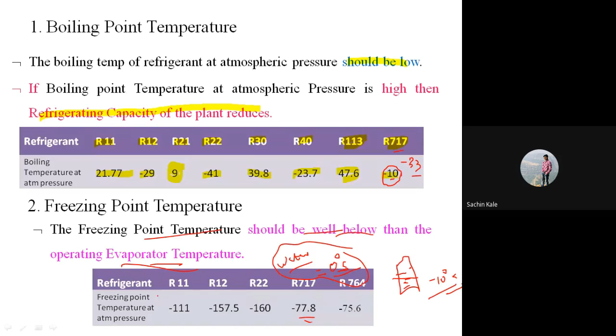One mistake I have observed here: the boiling point temperature of R717 should be minus 33 degrees centigrade. That minus 10 degrees centigrade is for R764, that is sulfur dioxide. For ammonia, the boiling point temperature is minus 33 degrees centigrade, and the freezing point temperature of ammonia is minus 77.8 degrees centigrade. That is the correction.